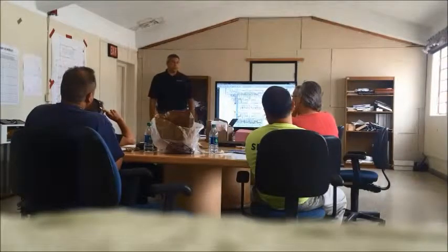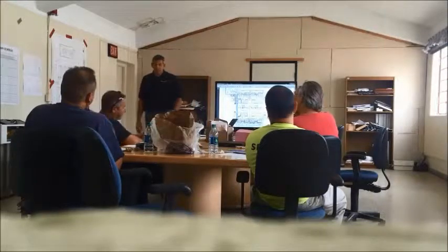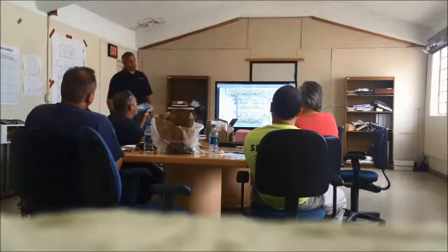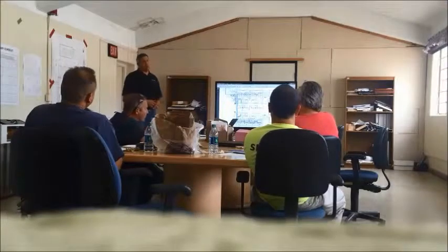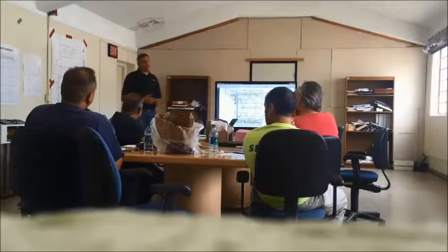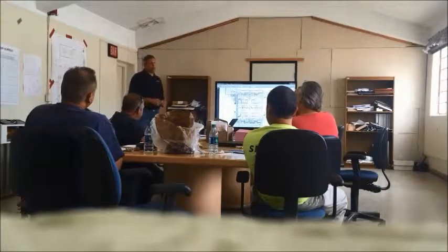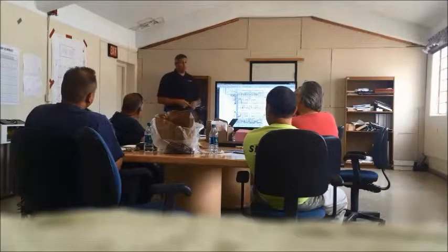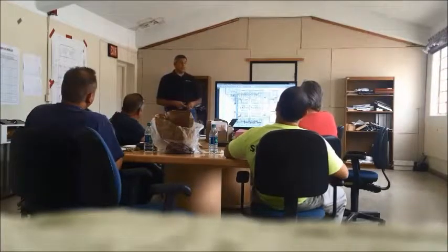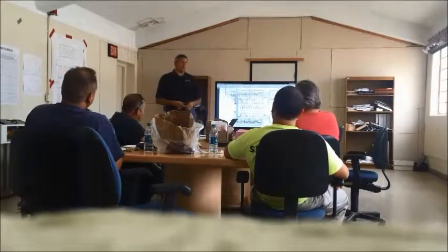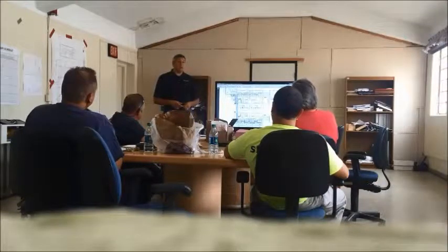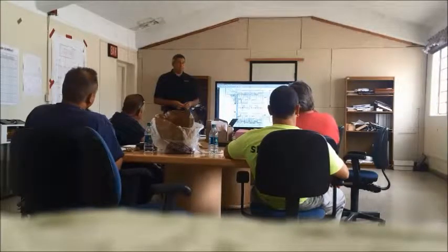We have a chill beam system in our office in Garden Grove, and I work specifically on it. One thing is we're driving chill water temperature down as far as we can to maintain efficiency out of them, but it's very critical as far as controlling. But at this point, it's 58 degrees. What you don't want to do, obviously, on the exchanger from low temperature chill water to high temperature chill water is to physically open it 100% and leave it in that mode, because then you're going to drop down to 44. Inherently you're going to be condensating on every one of the chill beam units, and you're going to make a rainforest in every classroom. Neat.